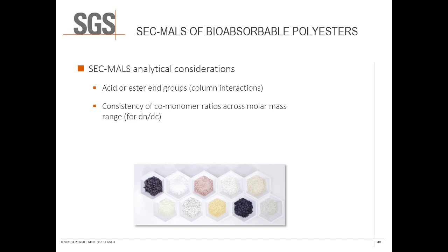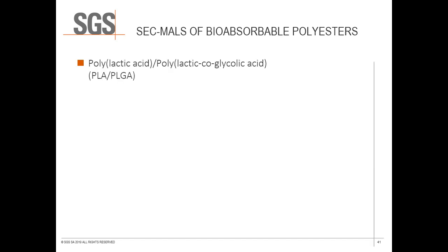the molar mass range. If inconsistent, then the differential refractive index increment may be different at various points across the polymer peak. This would contribute to error in molar mass calculations and must be considered from the start of an analysis. As an example bioabsorbable polyester analysis, we'll look at polylactic acid, polylactic-co-glycolic acid copolymer resin.